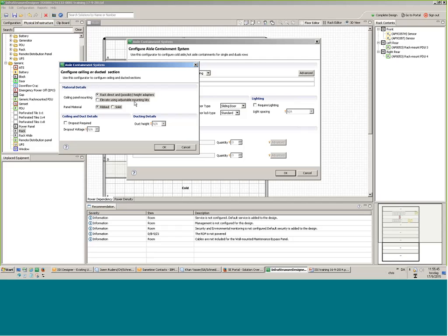If you have elevated, it's quite a lot of work, but if you have a third-party rack which doesn't fit right in, then use elevated. It's a possibility. The only thing which you have to be aware of, don't use the third-party rack on the corners, because our doors need the exact holes of the ISX racks.